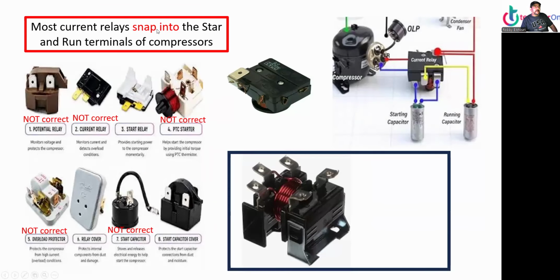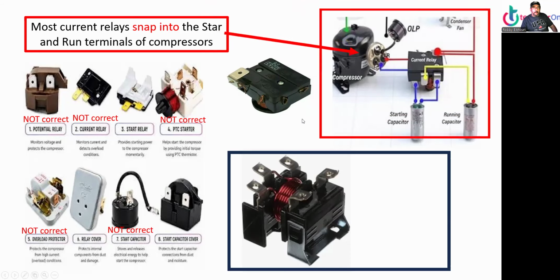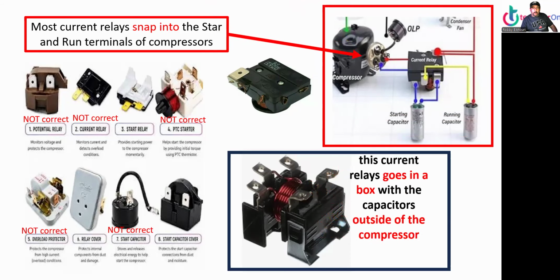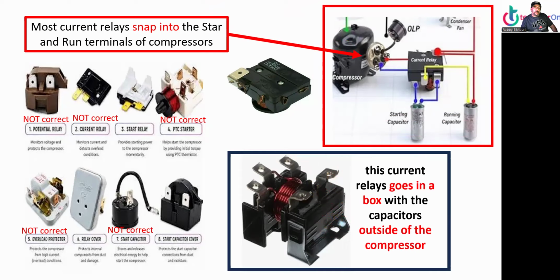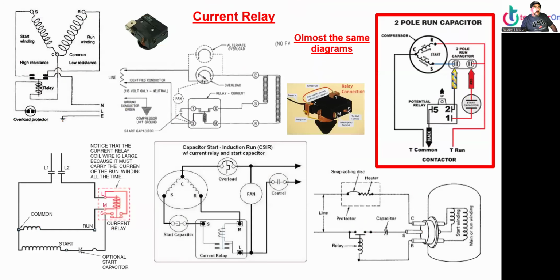Most current relays snap into the start and the run terminal of the compressor. You can see it snaps in there. There we go. But this relay goes in a box with the capacitor outside of the compressor. Right now, current relay, almost the same diagrams. Look how many we have. 1, 2, 3, 4, 5, 6. All right, but this one has no capacitor. This one has no capacitors at all.